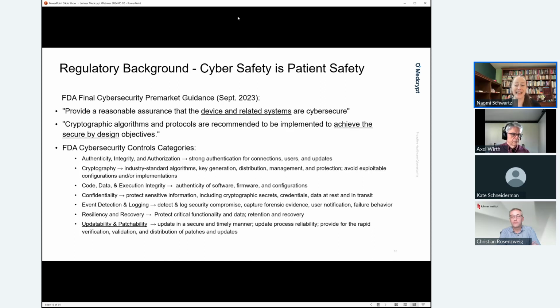Now, I want to emphasize device and related systems because you may have a medical device data system that is connected to your device that is not itself regulated, but cybersecurity for that system, because it is connected to the device, is still considered a requirement under the law, and FDA will be asking you about those related systems. That is very, very important because a lot of manufacturers like to think, well, the stuff in the cloud that's connected, it doesn't have a medical function, but it is connected and it could be the weak link that is used to attack your medical device. So FDA will be asking lots of questions about that.